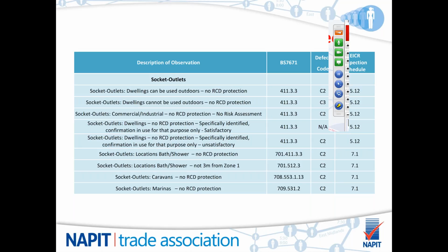We do have socket outlets in commercial and industrial where we don't, at this present moment in time, need RCD protection. But we do have to have a risk assessment that's been filled in, and that risk assessment should conclude, not on cost grounds, that there doesn't need to be an RCD, given that we have competent, semi-competent people there working with these sockets and they are aware of the dangers. But if there's no risk assessment, it would be a C2.